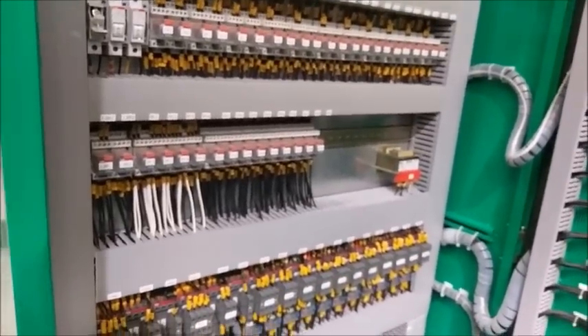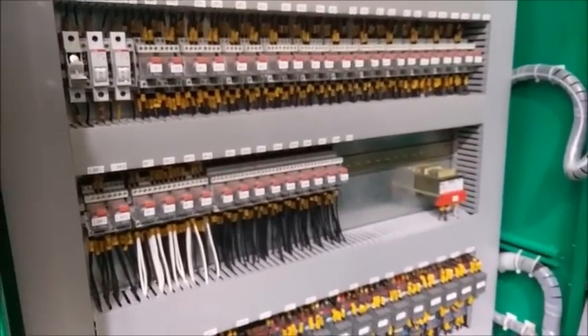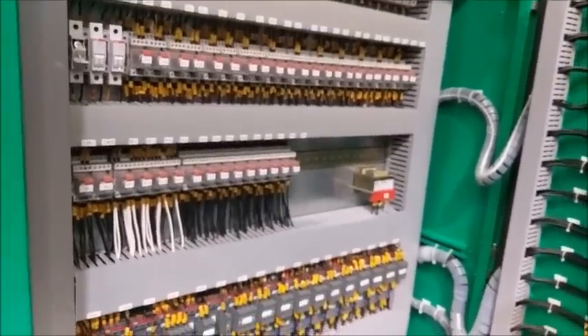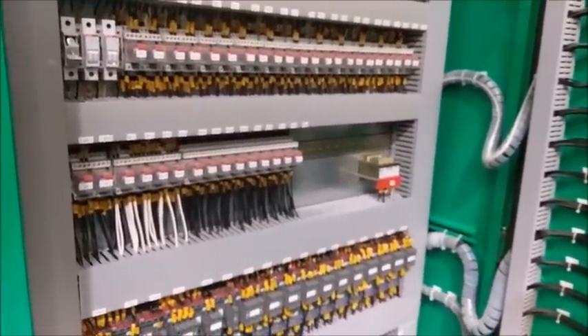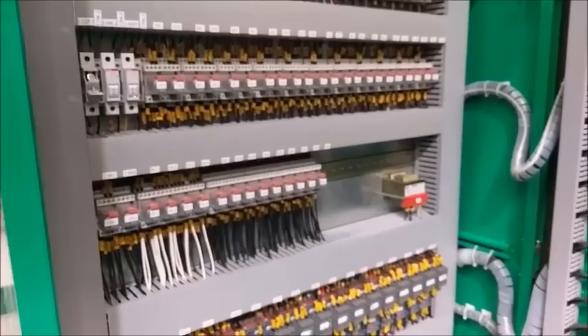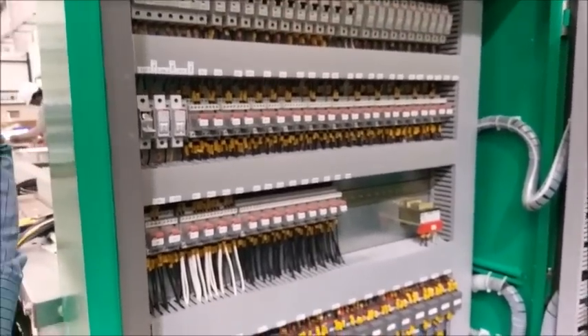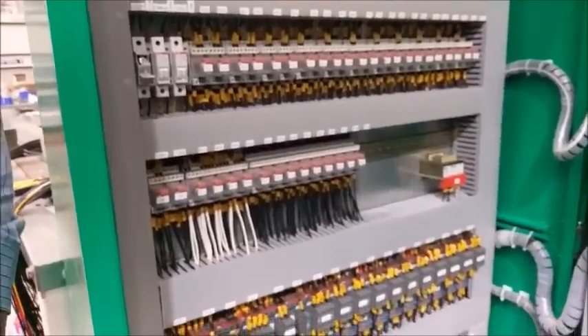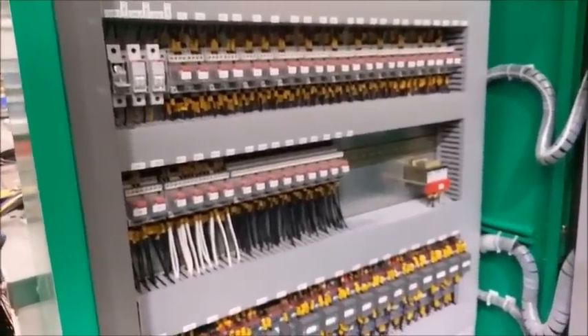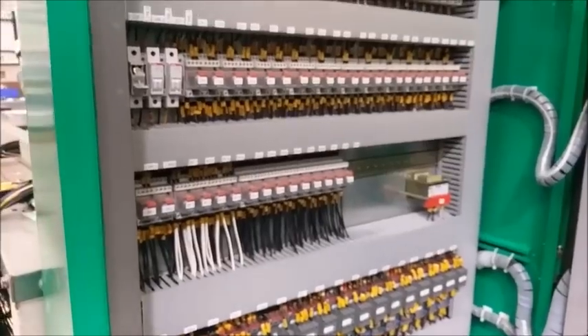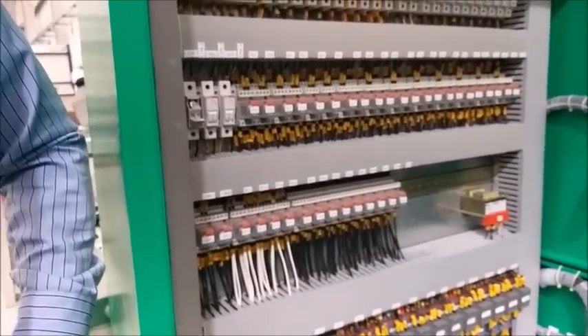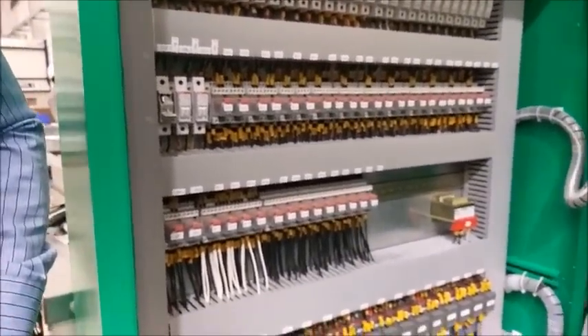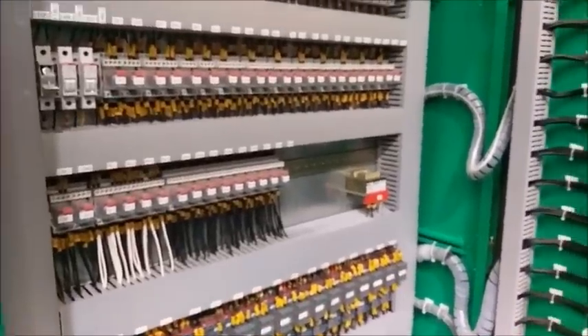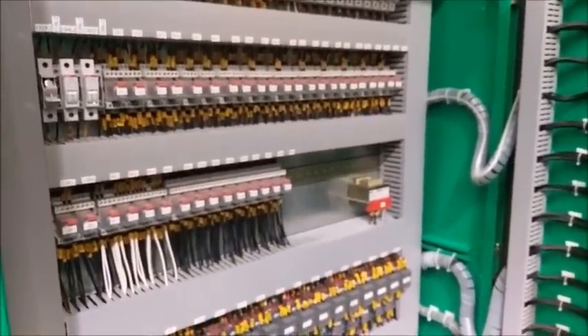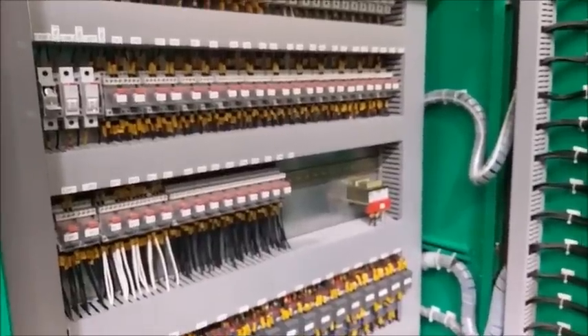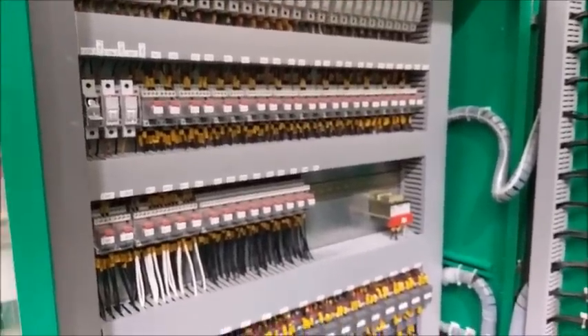This MCC that you prepared should be as per our load schedule of the MCC. Yes. You need the load schedule from us. Load schedule we need, and we need the sequence of operation, and what is the integration between the MCC panel and the fire alarm, if it's for exhaust fan or AHUs or FCUs like this, and also for BMS. There is integration between the fire alarm, BMS, and override panel.